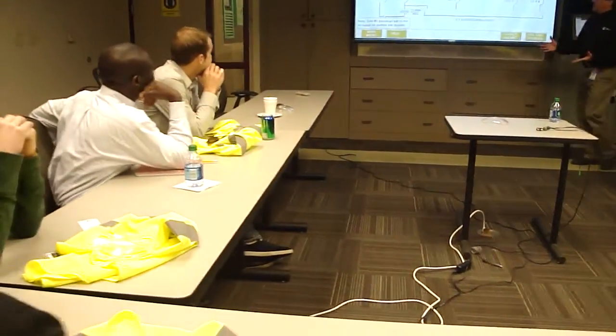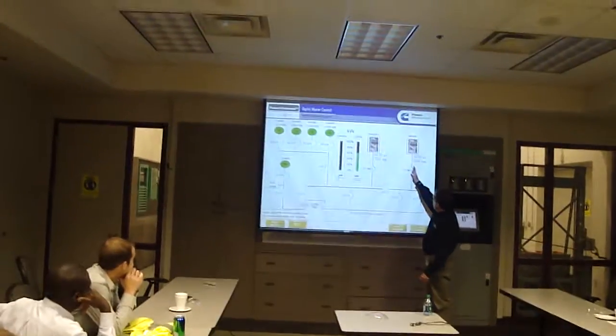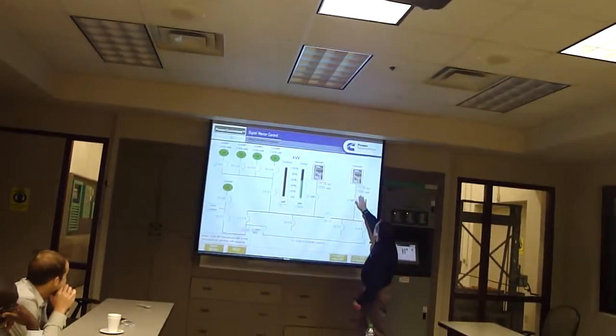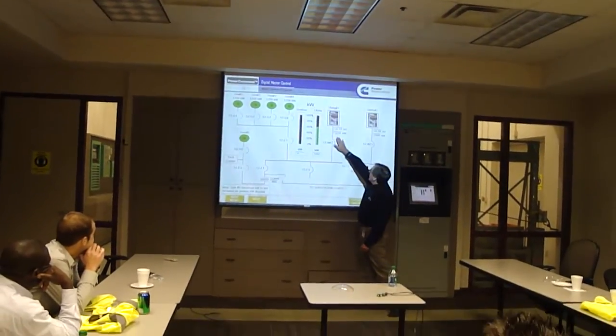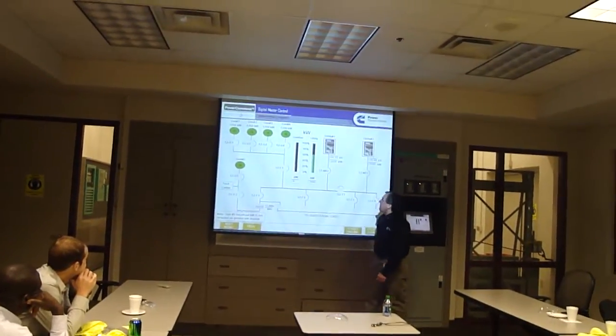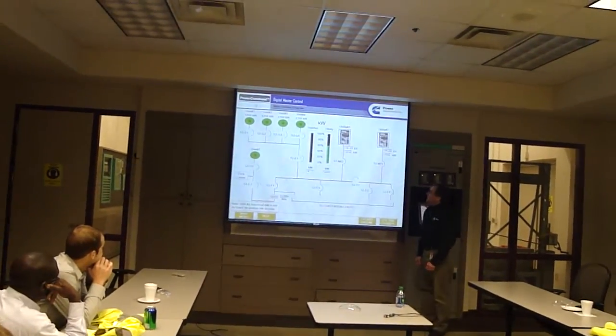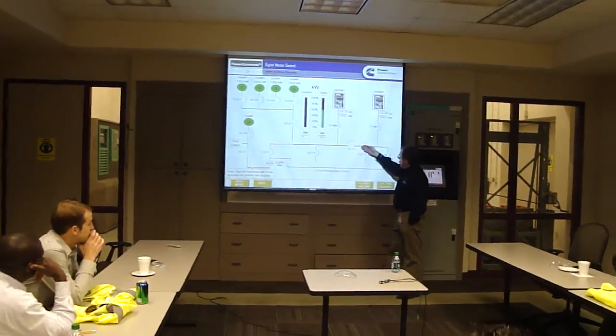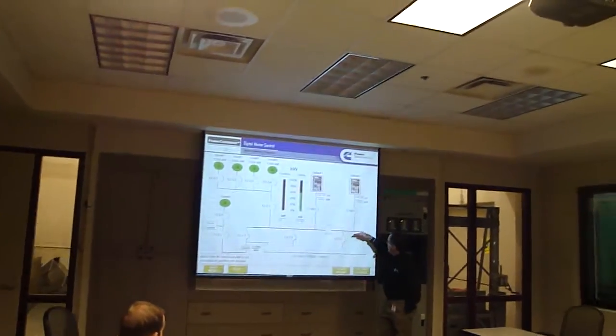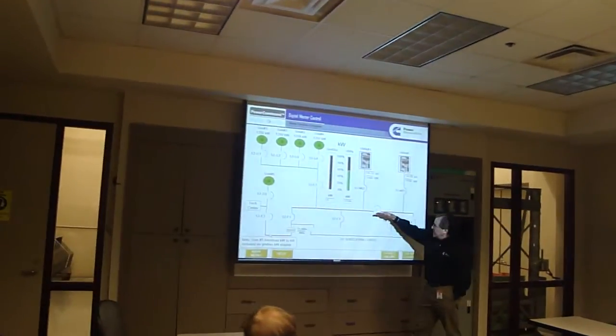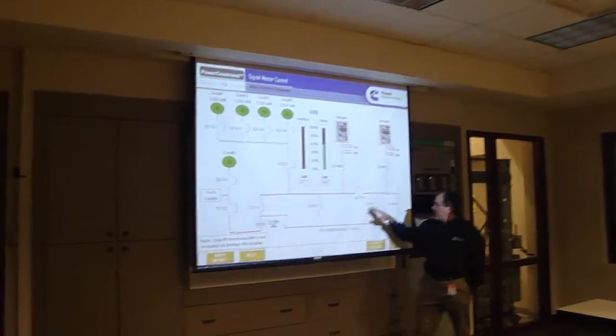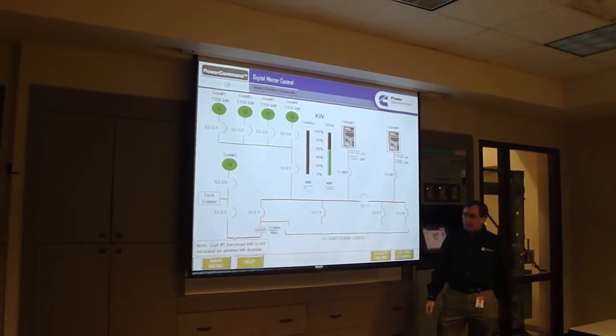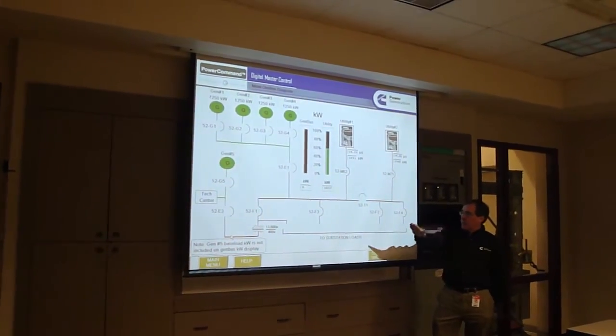Here's the one-line of our facility. We have two utility entrances. As you can see, they're running about 2.5 meg and 1.2 or 1.3 meg coming into the facility. They are basically a main-tie-main configuration, and this is the main bus that feeds out through feeder breakers out into the plant, through substations throughout the plant.